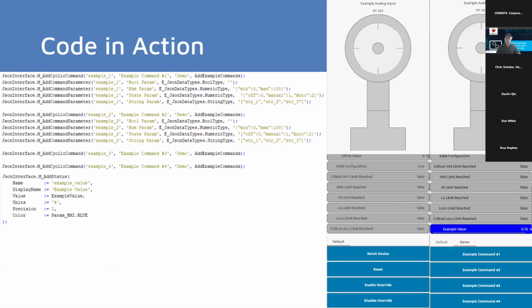So in order to add commands to the HMI, you'd call either an add command or an add cyclic command. The main difference here is the intent behind it. A cyclic command is only shown when a condition is true. In the code shown here, this add example commands Boolean allows the HMI commands to be shown or removed. Whenever it's true, it shows up, and when it's false, it's hidden. One quality of life benefit of these cyclic commands is that I don't need to hide or disable buttons from the operator during runtime. If I don't want an operator to be able to move forward, I can just get rid of the button. It prevents them from having to press it, it prevents me from even thinking that it's on the HMI and having to worry about handling it, and I don't have to worry about accidentally forgetting some user security level that allows it to go forward, or some condition that disables that button.